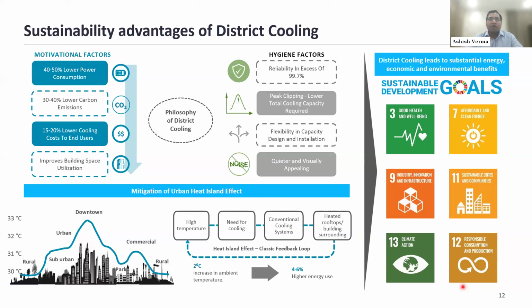There are other hygiene factors also related to district cooling. Reliability is very important, like I mentioned earlier. Reliability is in the range of 99.7%, or more than that. We discussed how the peak is clipped using thermal energy storage, and then we have flexibility in capacity design and installation depending upon the location.